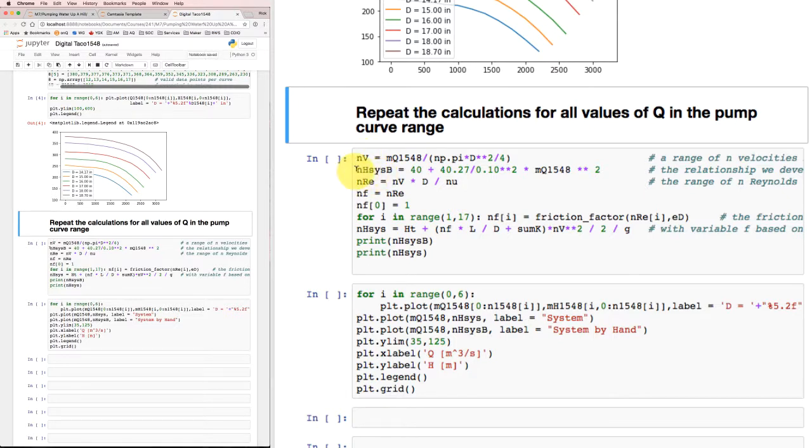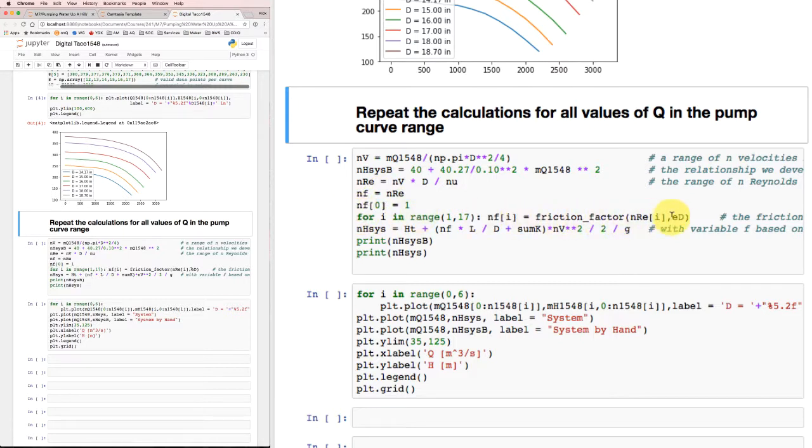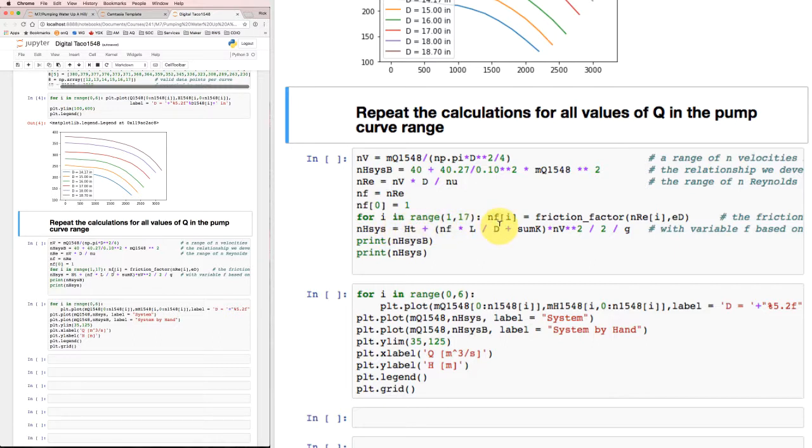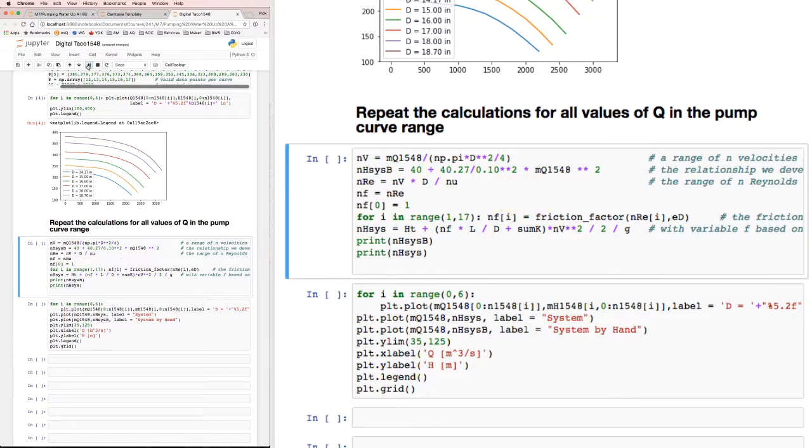I'm calculating my system head based on that parabolic equation that we developed before. Then I'm calculating a whole array of Reynolds numbers corresponding to the array of different velocity values, getting a whole collection of friction factors dependent on that range of Reynolds numbers and my relative roughness, and then calculating a whole range of system head requirements based on my elevation change, the friction factor times L over D plus sigma K times V squared over 2G. So exactly the same kind of calculation as I did before. I'll run through that and see what I get.